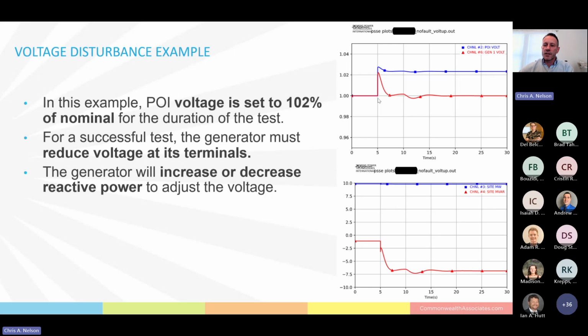And the red line is the generator that's a couple transformers deep into the site. It spikes to 102 and then it tries to fix it. And that's what it should do. It needs to try to fix the voltage. It's not going to be able to affect the utility much because the utility is so much bigger, but it has to try. And if enough generators behave the right way, then the utility will go back where it should.